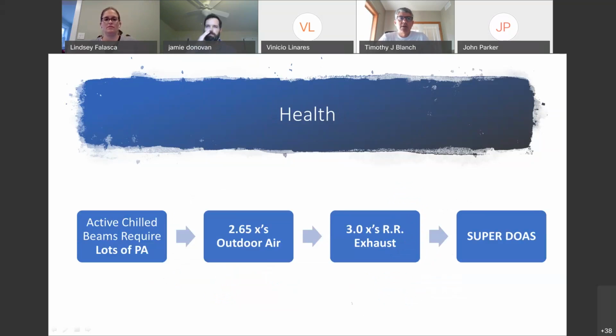Next. All right. So the active chilled beams require what? A lot of primary air, PA, primary air. This was the first thing that we really had to wrestle with in design. And what it caused us to realize is that if we were going to use outdoor air, we would need about 2.65 times the minimum ventilation requirement for outdoor air if we were to make all the primary air outdoor air. Fresh outdoor air, not a mixture of that with some recirculated air.